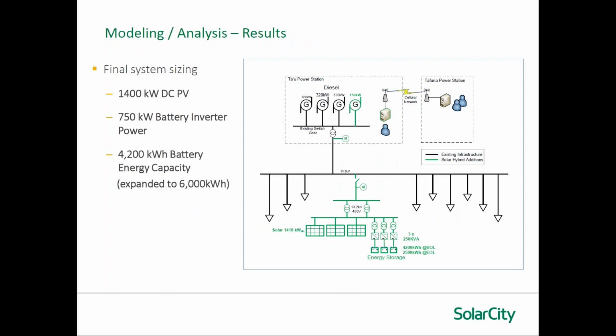The final sizing for this system was 1.4 megawatts, 1,400 kilowatts DC of PV with a 4,200 kilowatt hour battery. As I mentioned, that was later expanded up to 6,000 kilowatt hours, and the battery has an inverter power of 750 kilowatts, mostly to be able to capture the load. The load also captures the PV into the battery, and the PV is also directly serving the load, as I showed in the prior charts.